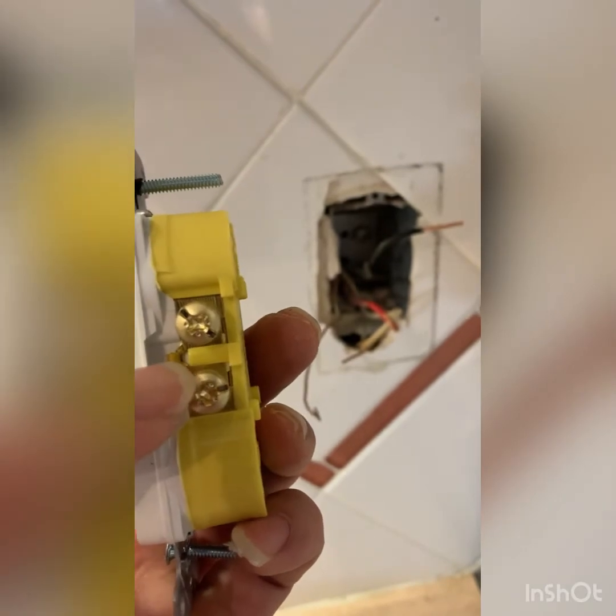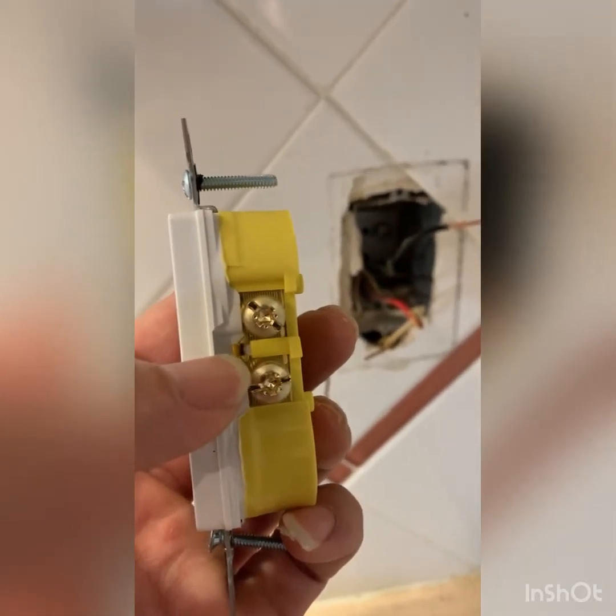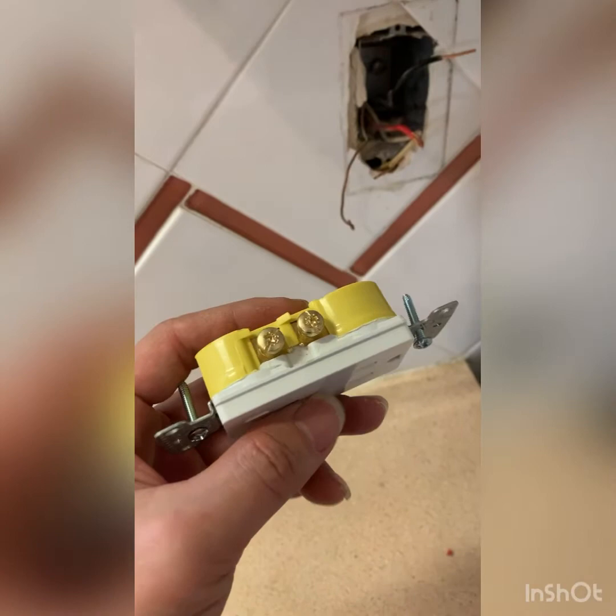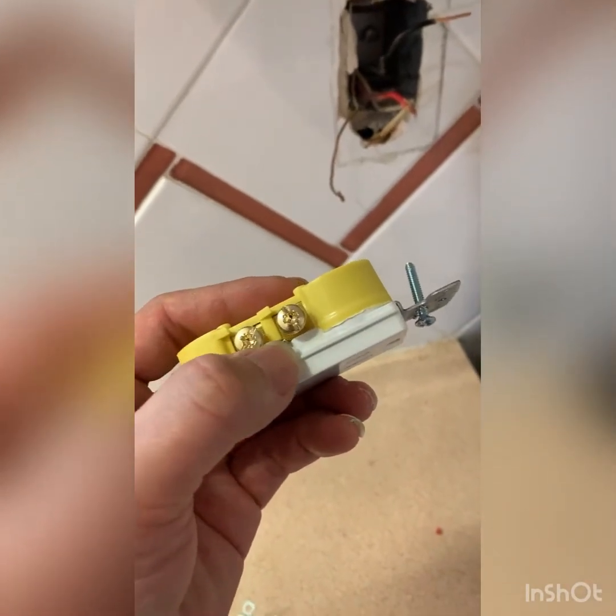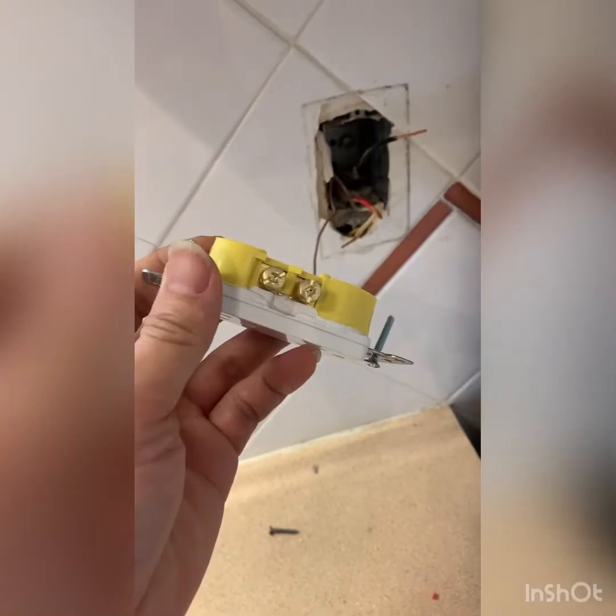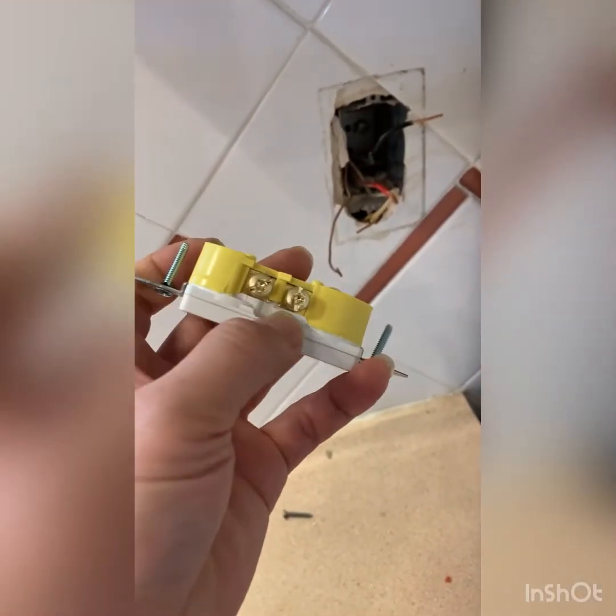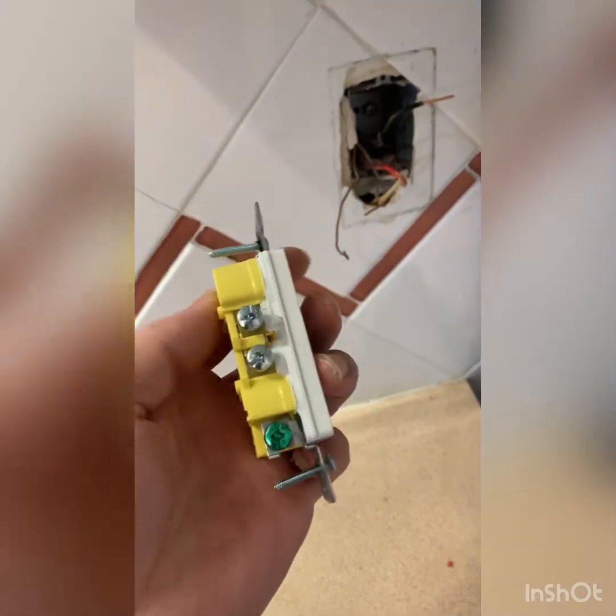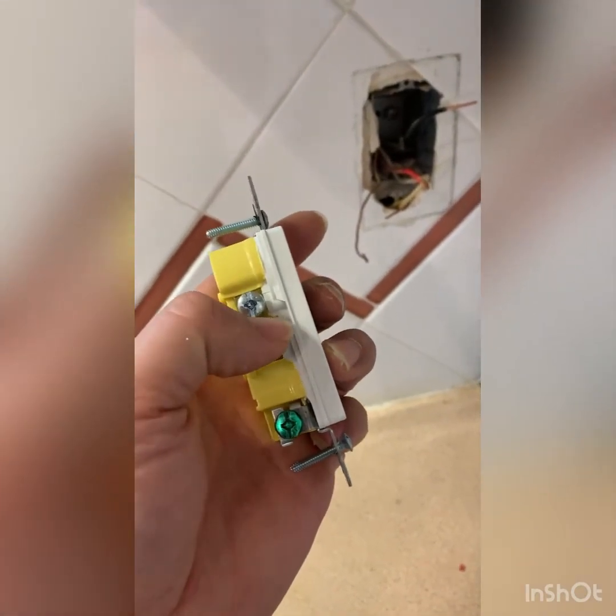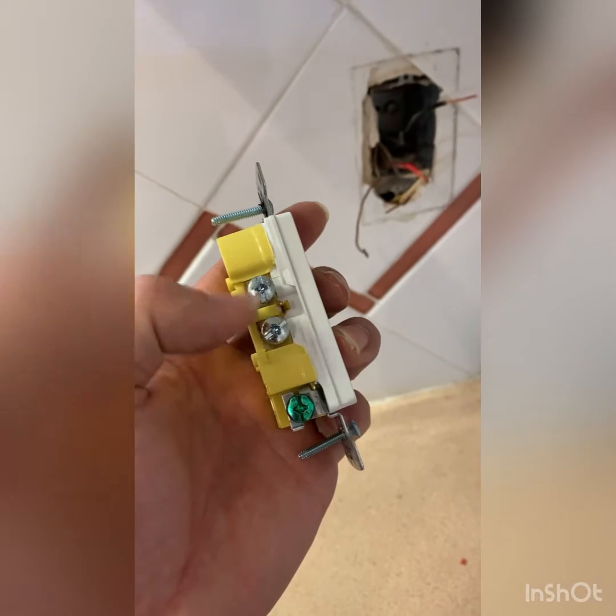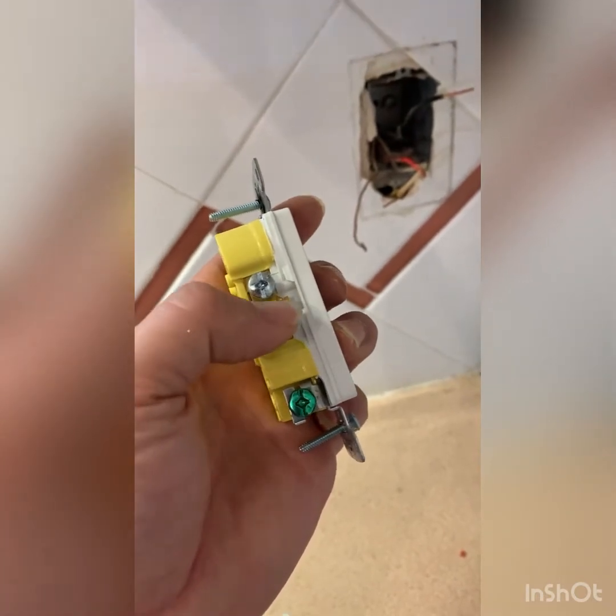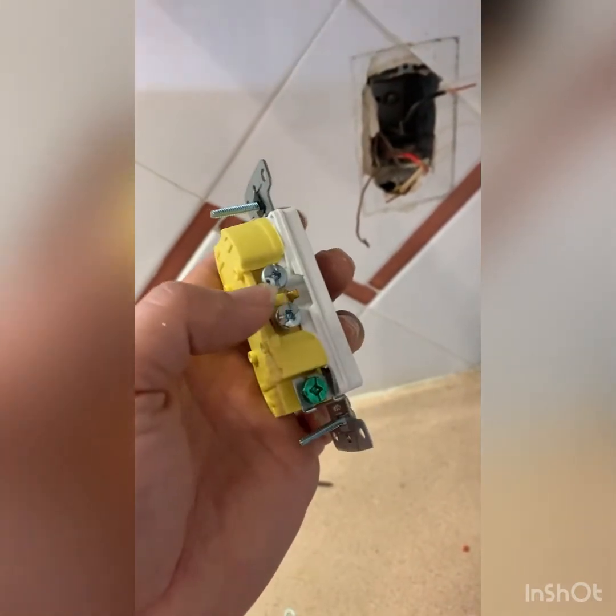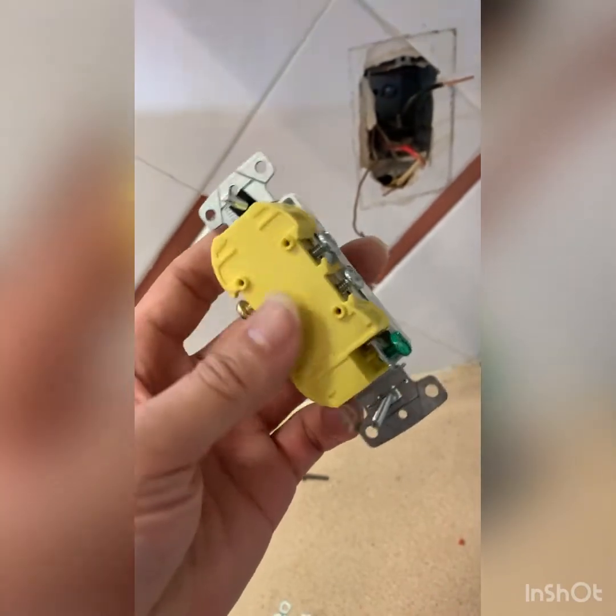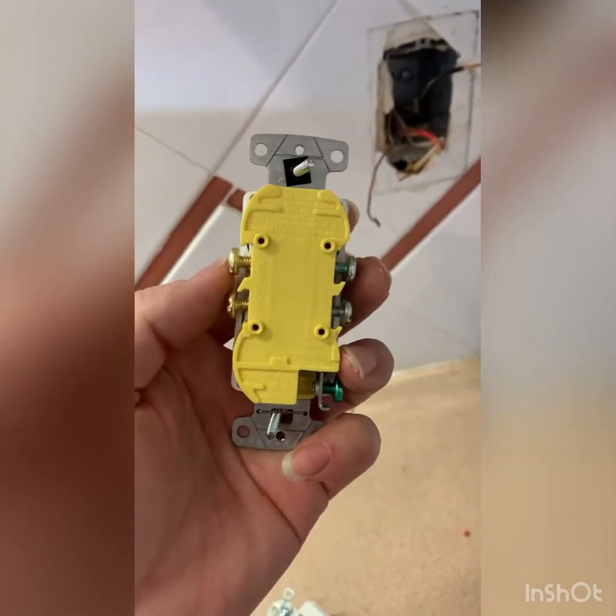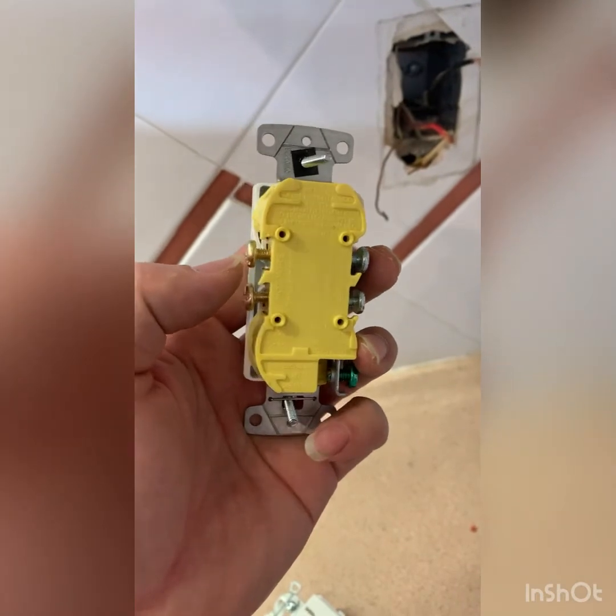But don't forget to take this off, snap this bridge off. See, I already snapped off the bridge like this. I'm going to connect it back. And remember, just do it on the hot wire side, okay? You don't snap off the bridge on the neutral side, because it's shared neutral. Don't touch here, this white colored one is neutral. You can see the difference. This golden color is the hot wire.